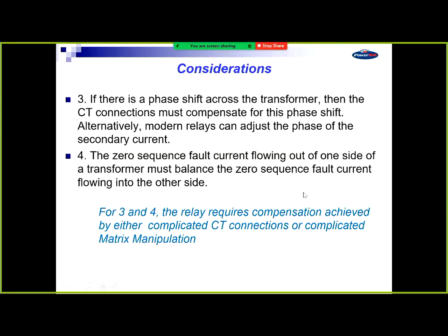If there's a phase shift across the transformers, we used to have to compensate for that in the CT wiring, the same with the zero sequence. We don't need to do that now. They've got mathematics basically in there, a matrix arrangement that takes care of that. You tell it what matrix you want it to use, and it'll account for your phase shift and your zero sequence source.